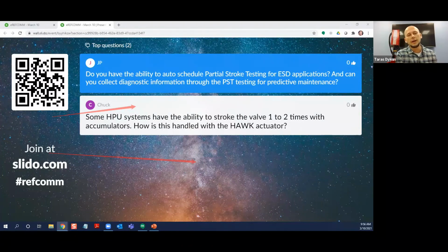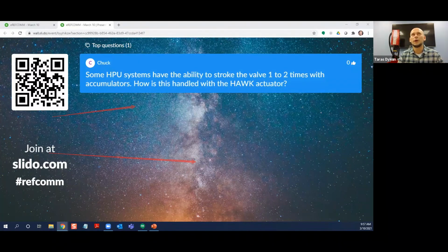So next question: do you have the ability to auto-schedule partial stroke testing for ESD application, and can you collect diagnostic information from the PST testing for predictive maintenance? Simple question, yes, we can do that. We can include this type of feature. This is an additional feature. However, yes, that's quite simple, and we can do that. And you can send this signal back to the DCS and track this kind of repetitive partial stroke testing. But for HPCUs here, if we're talking about the ESD system on the current FCCU setup, we want to do online testing and make sure everything works. So this is basically just a part of the ESD system for these FCCU type of valves.